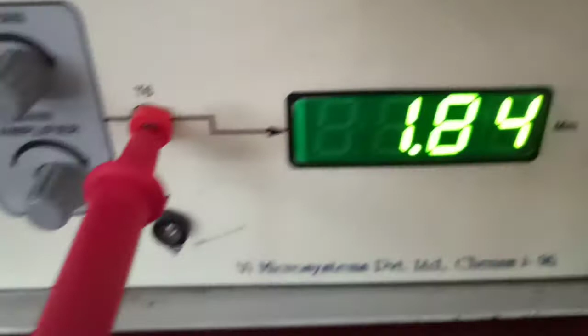If I note this displacement, it shows 2 mm - this is my actual 2 mm displacement, from 0 to this line. For this displacement I get a reading of 1.84 mm digital displacement, and the voltage I get is 0.915. I will note down this reading.